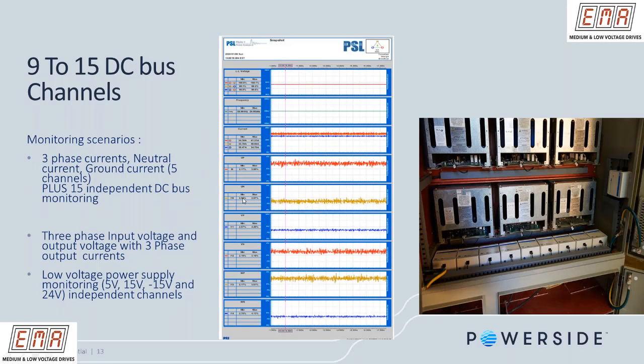And our DriveScan, like I said earlier, can take from 1 all the way to 15 different DC buses, or in our case, power modules, right? On a cascaded bridge topology, we have single phase drives that are cascaded to produce the 4160. So we can do up to 15 of these, okay? And monitor each power cell and then feed it back to the intelligent part of the DriveScan. We can look at the phase current, neutral current, which is your ground current, plus 15 independent DC buses. These are the DC buses we're looking at, as you can see here. So we can determine the ripple, and we can determine the health of the power module from DriveScan.